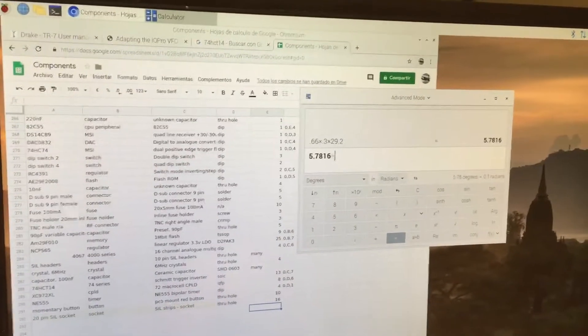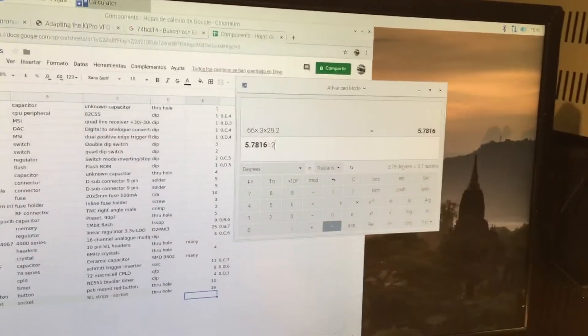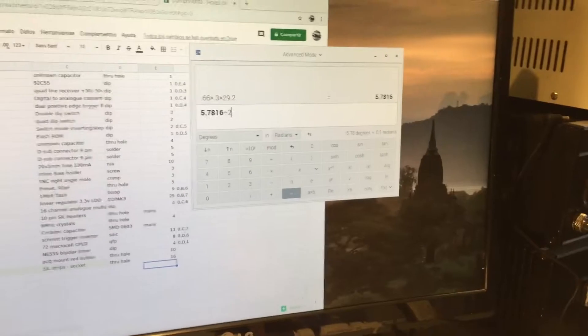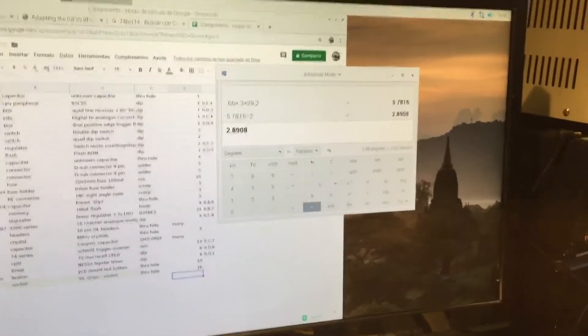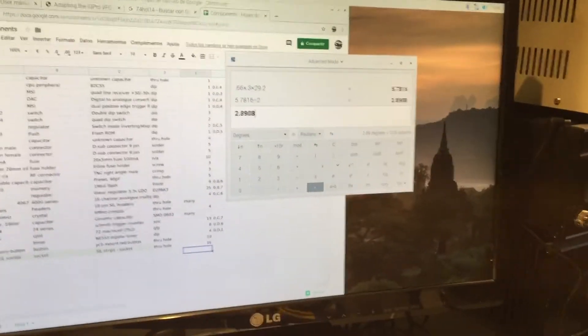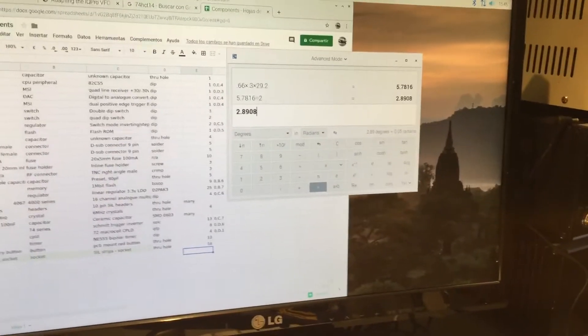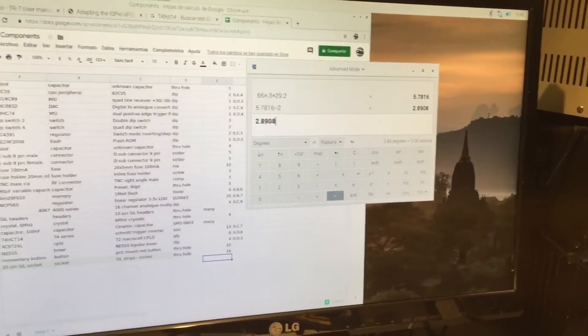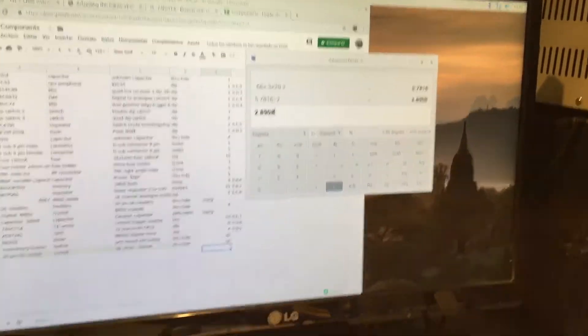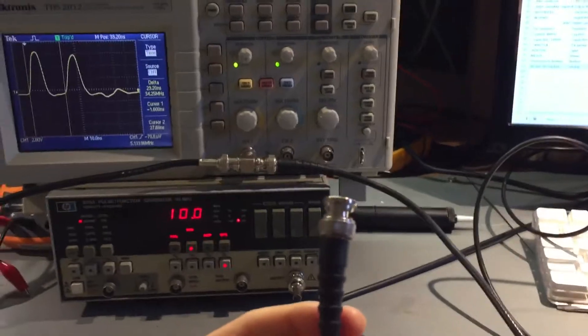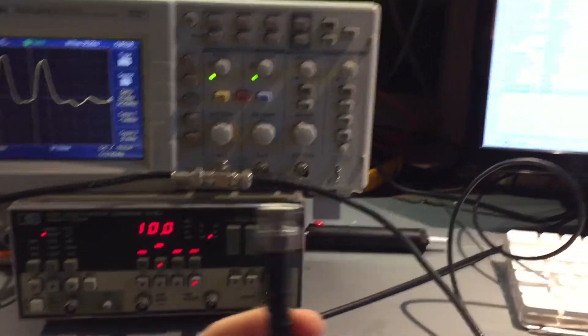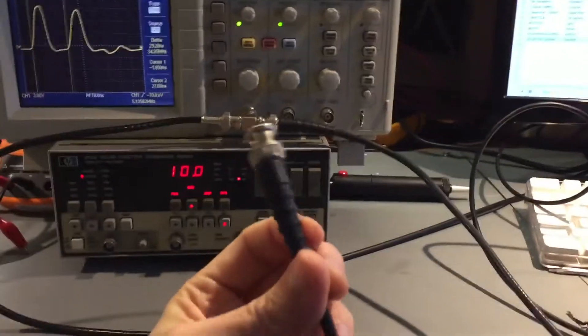We have to halve that to find out where the open end of the transmission line is. And it tells us it's 2.89 meters down the coax. And I can tell you now, this is actually... That is pretty much spot on.